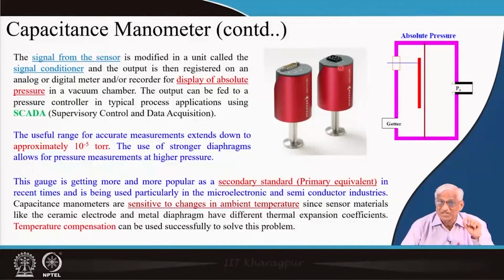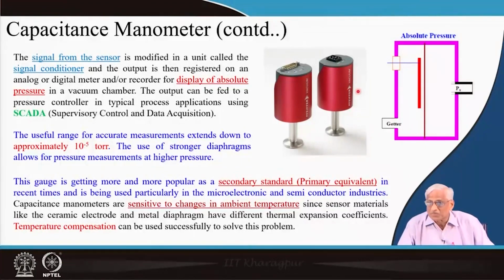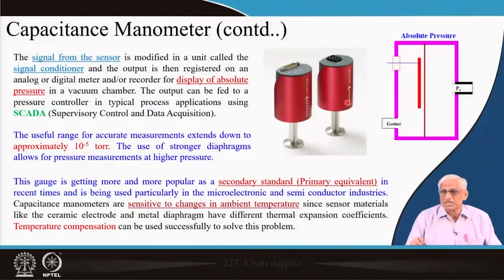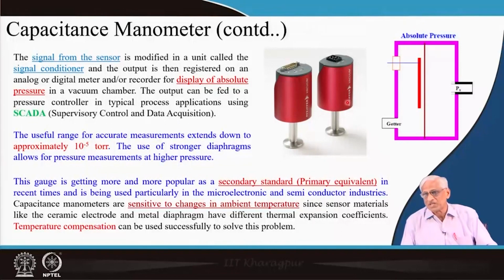With this instrumentation - mechanical design, suitable metallurgical processes, making a diaphragm, and understanding natural deflections - if you do all that well, you have a very good business, important for day-to-day applications, especially semiconductor applications at medium pressures. With temperature compensation etc., most problems are solved, and these gauges can be used as primary gauges if you can afford them, or otherwise as standard gauges. With this, we have completed deflection type gauges, both Bourdon and capacitance gauges.